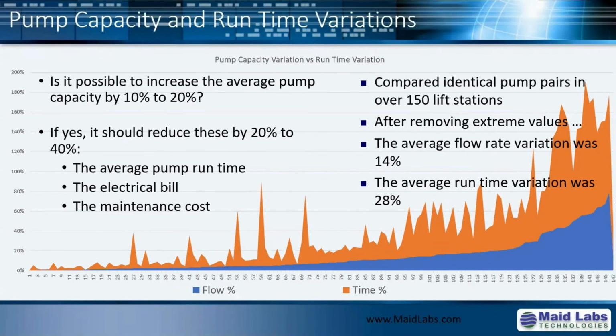One thing I've done recently, I analyzed 150 lift stations. My goal was to figure out, if I have 1% of difference between my pump capacities, what's the variation that I have in runtime of these pumps? And as a rule of thumb, I can tell you for every 1% of difference in pump capacity, you have 2% of variation in runtime. This is true at 1%. This is true at 20%.